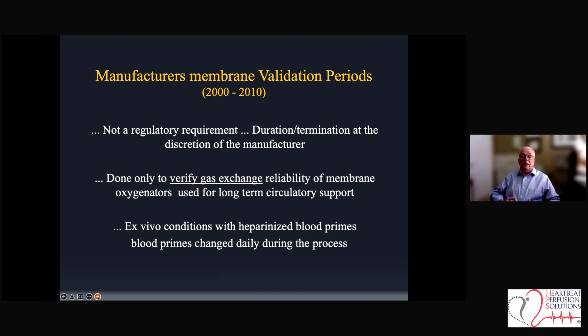And so I'm sure you've heard most of the manufacturers talking about their validation periods for individual oxygenators. Some of them will be validated for 5 days, and some of them will be validated for periods of 15 days, I believe. The FDA never recognized validation periods. They still stuck with their maximum of 6 hours per use. But as you know, with ECMO, it's always much longer than 6 hours per use. But that was the responsibility of the physician to take on, even though they were using it outside of the FDA regulations.